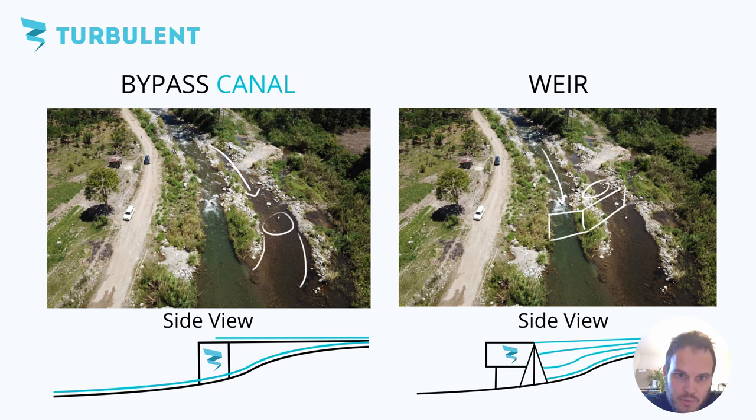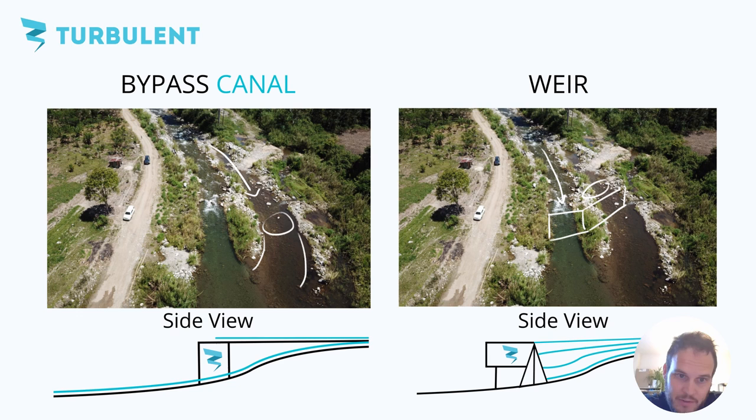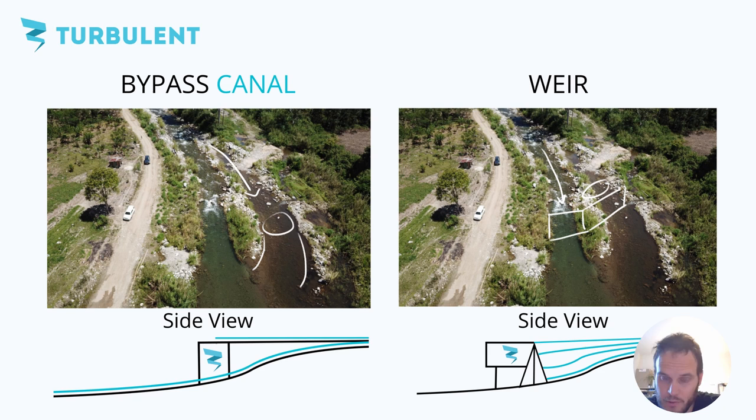In the case of a bypass you will put the water that you want to use for hydropower in a side canal that has a lower gradient than the main river and you will keep it at a higher level until it reaches the turbine. Then you will let it drop through your turbine and go back to the main body of the river. In the other case where you install a weir you will have this dam that will increase the water level of the river all the way upstream and right after that you will have your turbine that will be using that immediate drop of height.